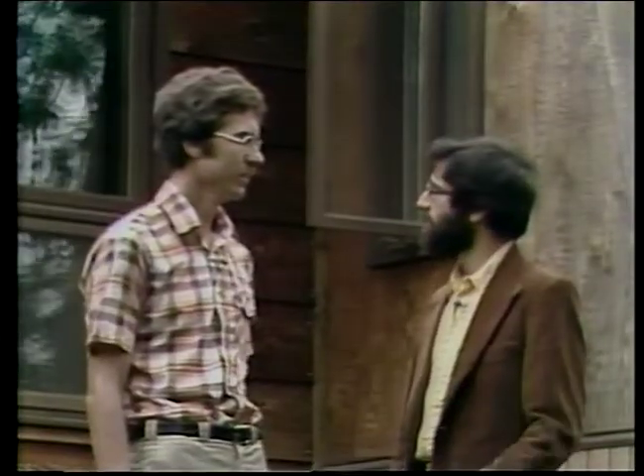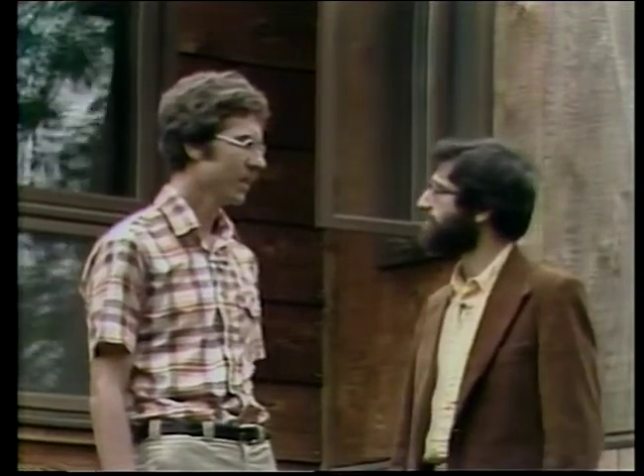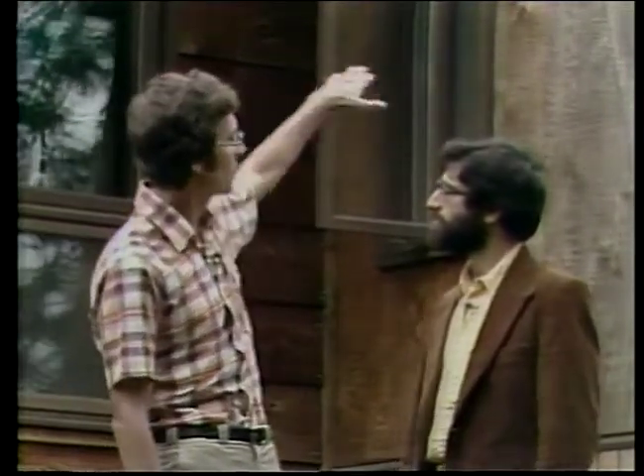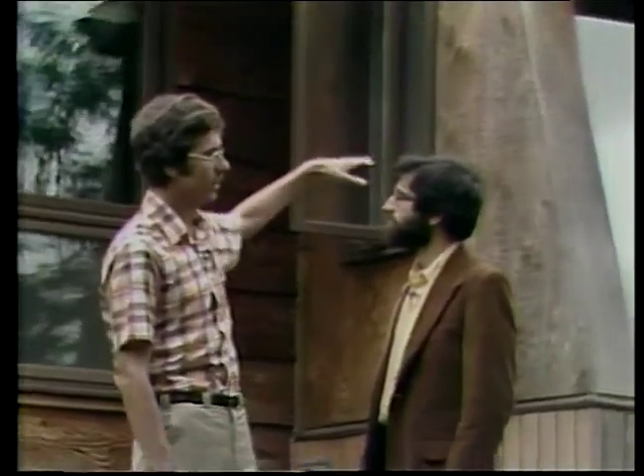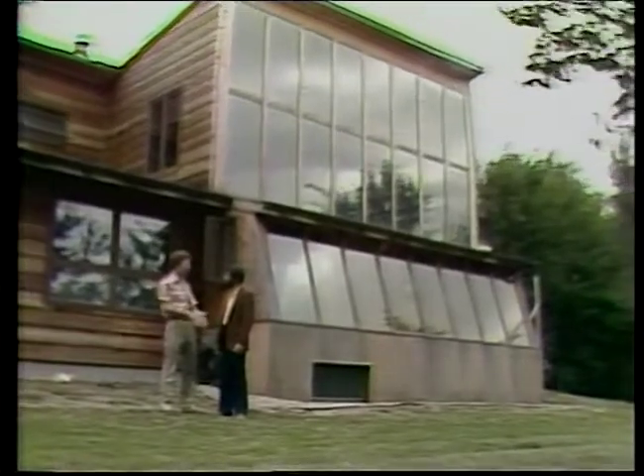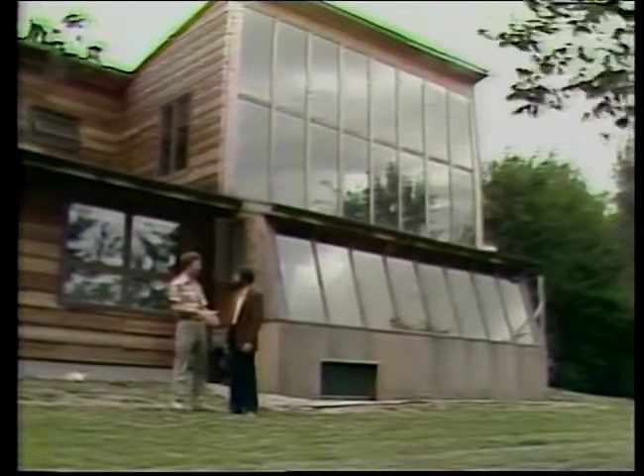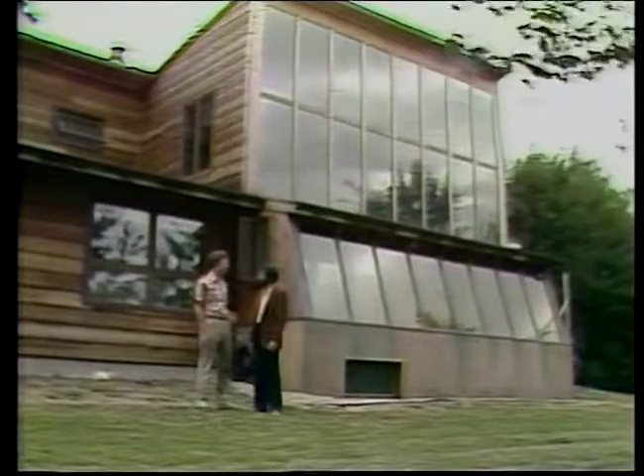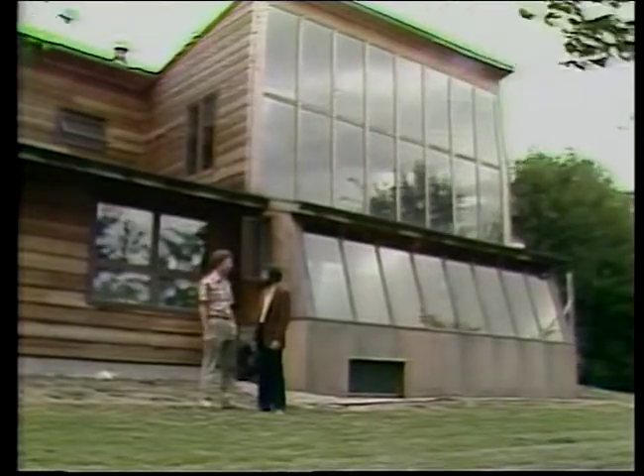Now, how does the air move through the collectors? The air is introduced at the bottom of the collector array. It is then heated and rises naturally to the top. Running across the top of the collector, we have a horizontal duct with the main trunk that connects to that, goes all the way to the basement, and there's a fan connected to that, and it'll pull the warm air from the top of the collectors down into the basement. From there, it can be either blown to the house or blown into storage for retrieval later.